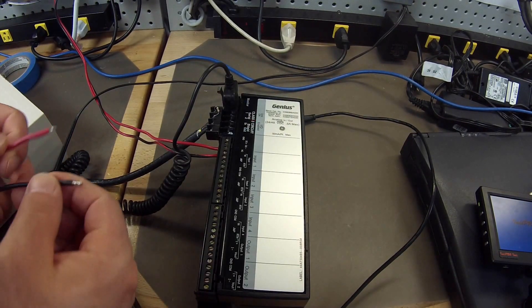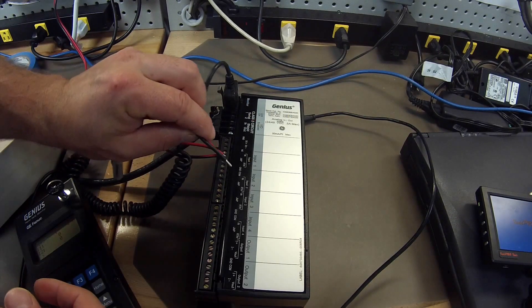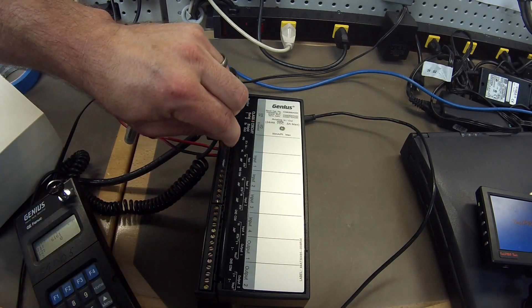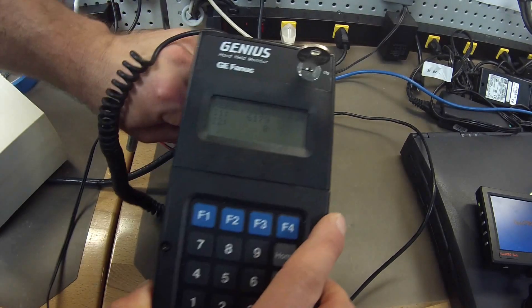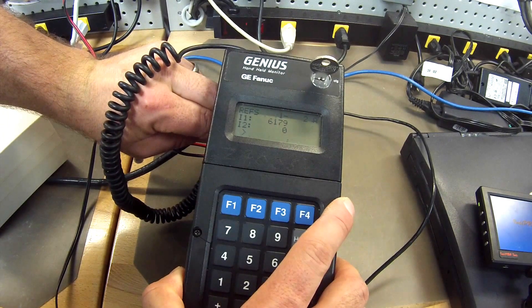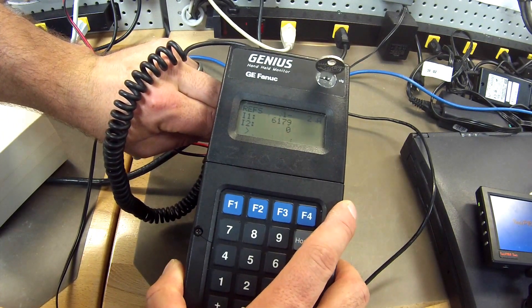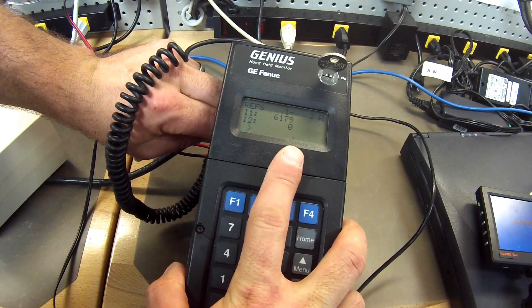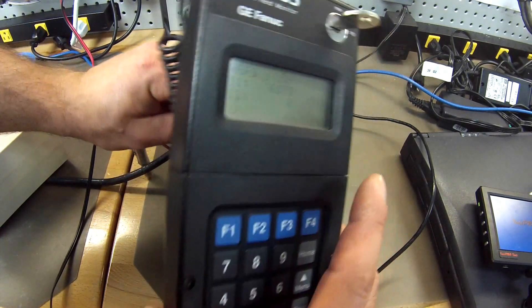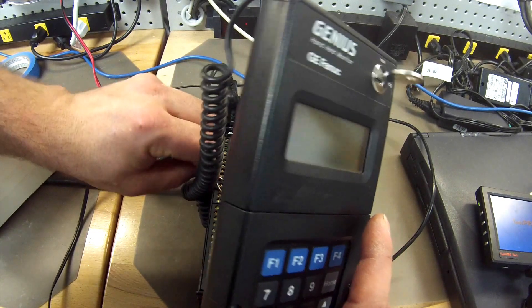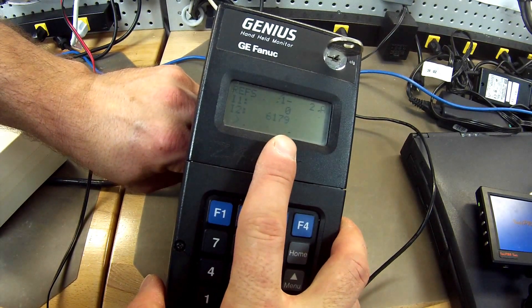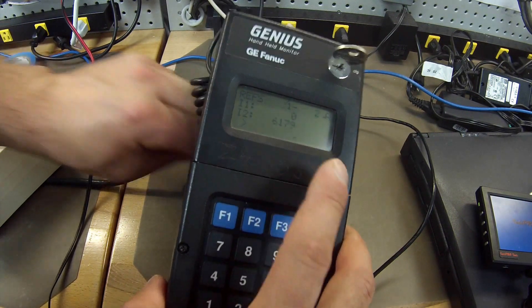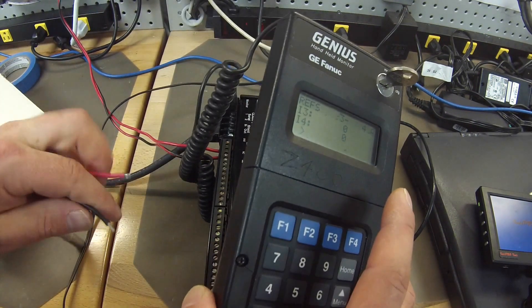In and return, and I am looking at input number 1. If you look at the monitor it is 6179. Now all my scaling is the same for every channel. So I am looking for a similar figure for input number 2. 6179. So I have got two channels that are reading the same. That is a good sign.